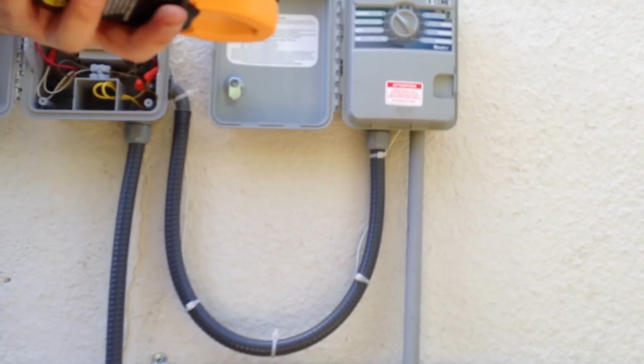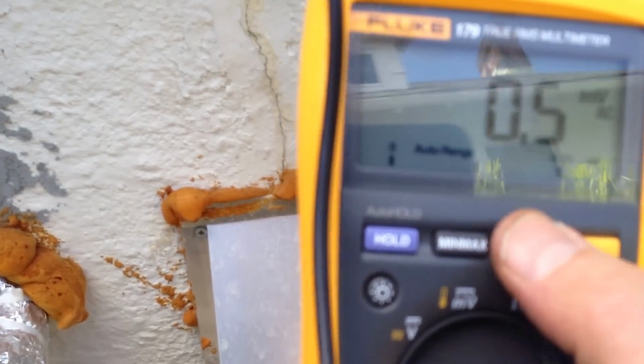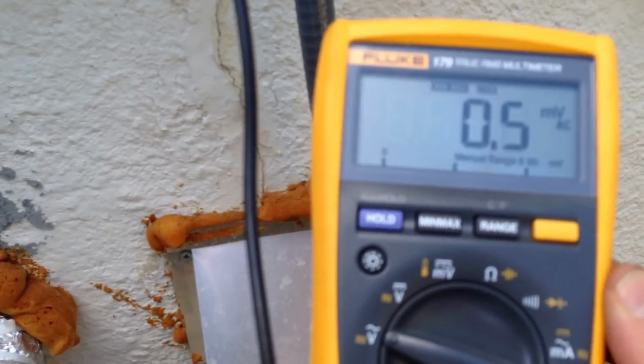So we're going to clamp it around. I just want to make sure you can see it. Here's the multimeter. Here's the clamp. Here's the relay box. And we're going to clamp this around one of the wires, the red wire that you see. You only want to clamp it around one wire. If you clamp it around more than one wire, it's going to mess up the readings. You're not going to get a real reading. And we're going to set the multimeter to measure the minimum and maximum that's used. And we'll turn this thing on and check it out. So for the pump, you just hold this button and it'll turn it on.